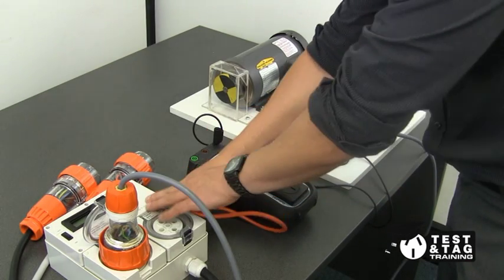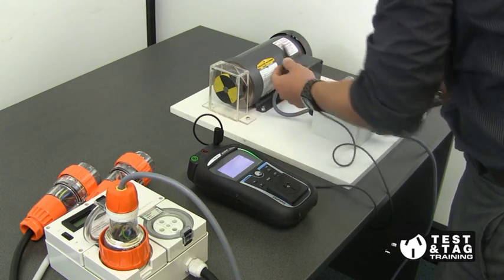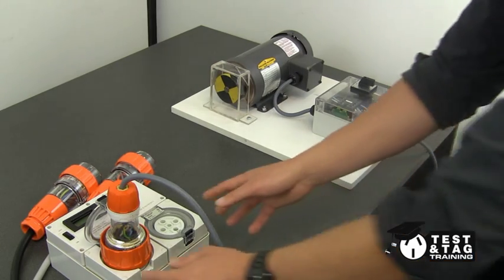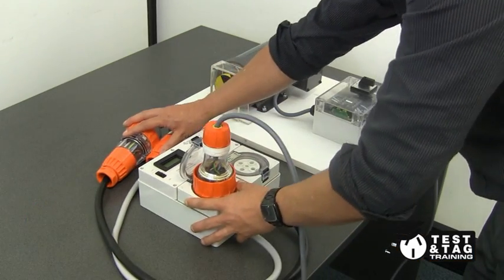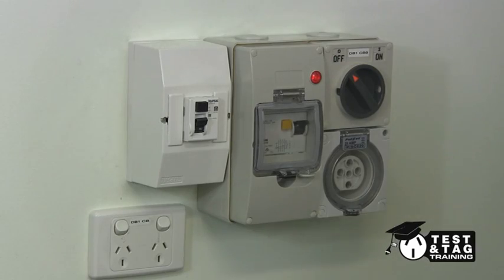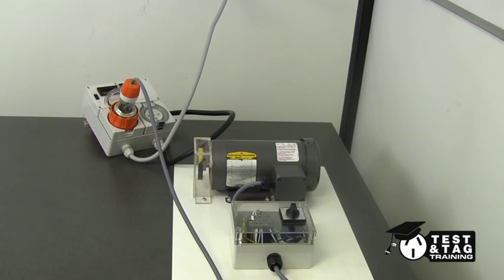Once this task has been completed, unplug our Metrel tester. Selecting the correct mains supply to our three-phase leakage tester, plug it into the three-phase GPO. This is what our setup should look like.